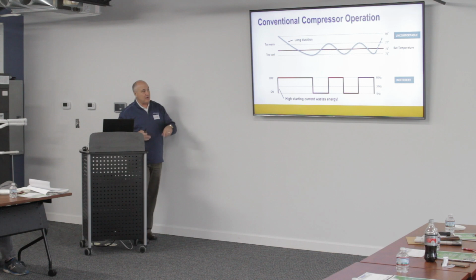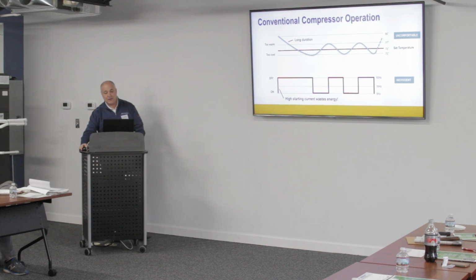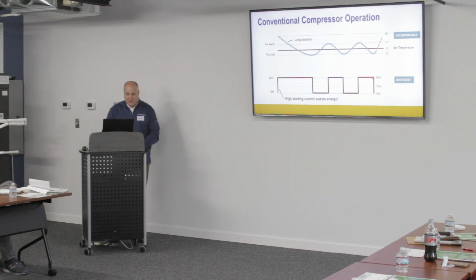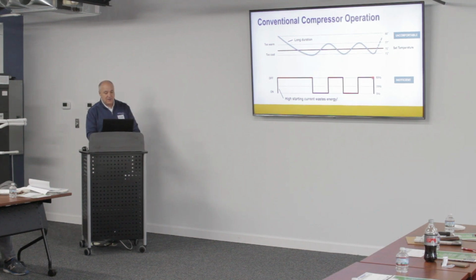These also run on AC voltage current, and they run on 60 hertz of electricity, which is the norm in the electric stratification of how we use our power in the United States. The ductless systems from overseas run a little bit differently. First off, the compressors inside of them aren't AC voltage, they're DC voltage compressors, and they run off a PAM controller in there. So they're very efficient.